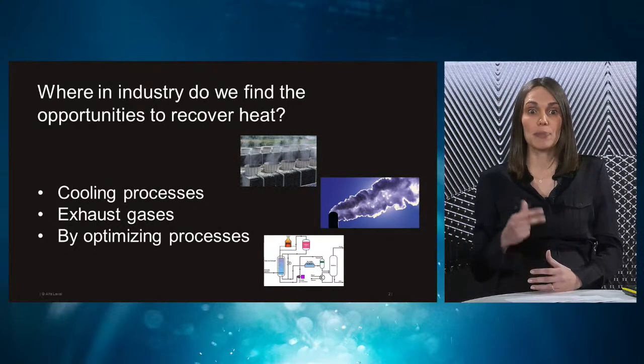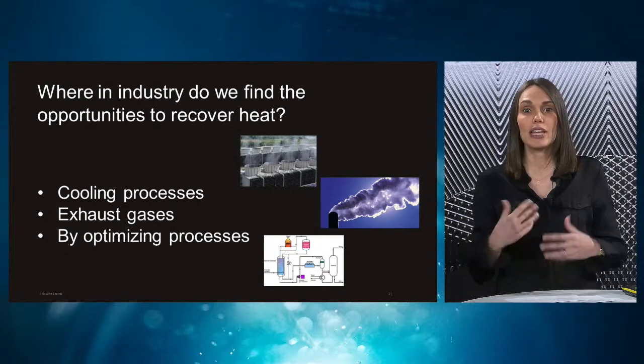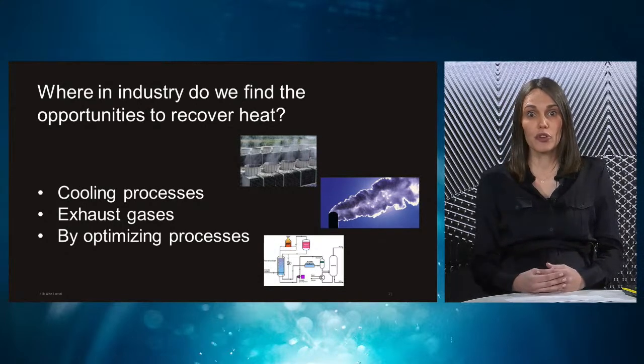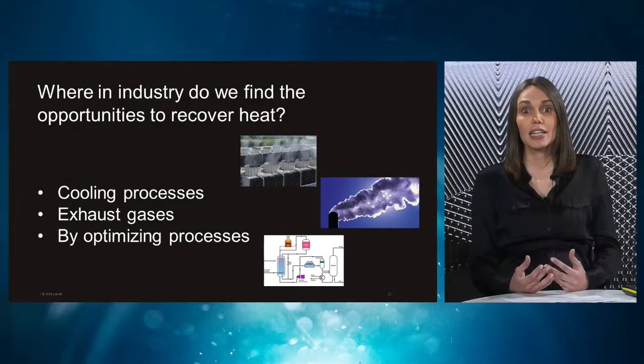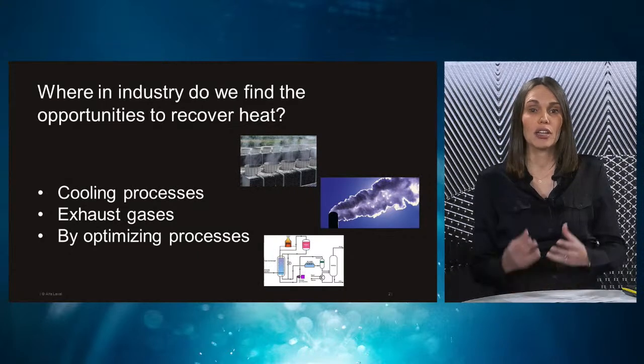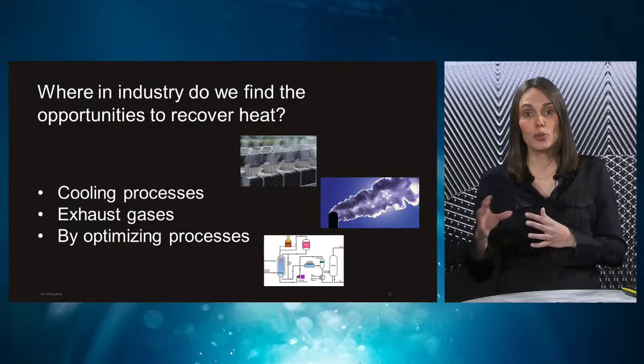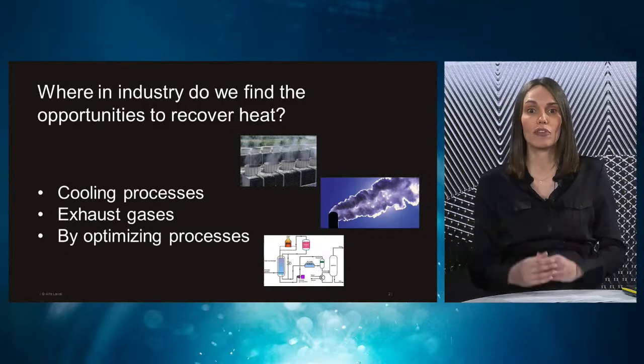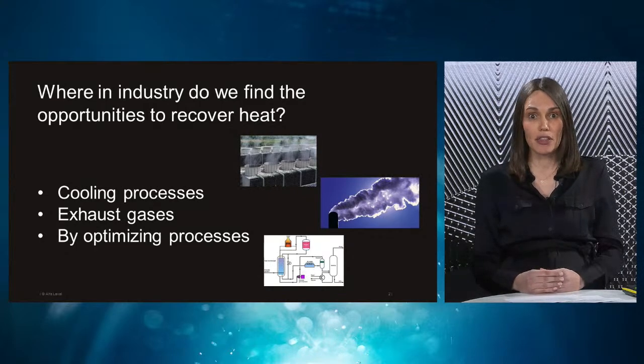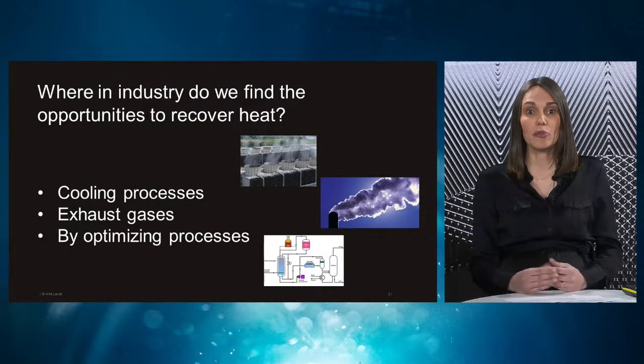We could also recover heat by optimizing our processes, and here we need to design processes from the first place with energy efficiency in mind. It could, for example, be around feed effluent interchangers, where a hot output from a reactor preheats the incoming feed. It could be by increasing the number of effects in an evaporation system, and by that we reuse the steam one extra step, or we can optimize around air compressors or steam and hot water boilers.